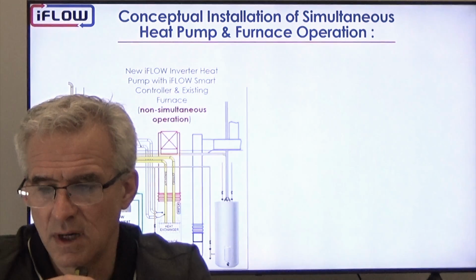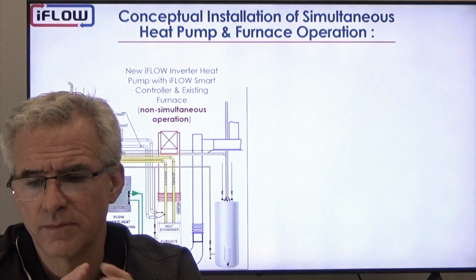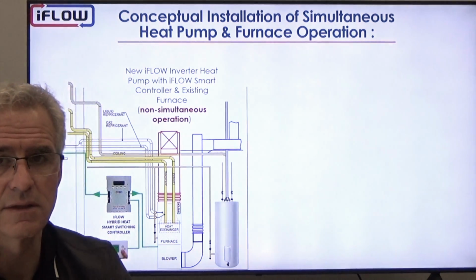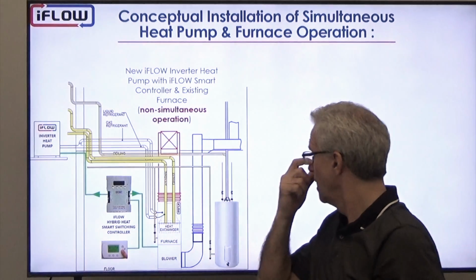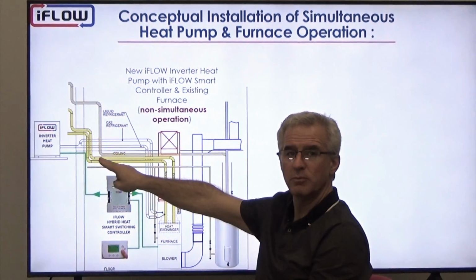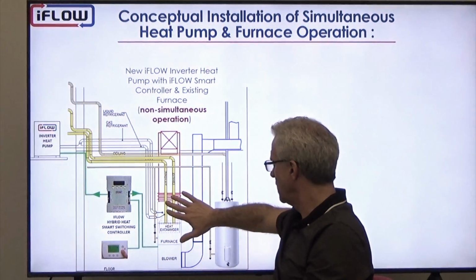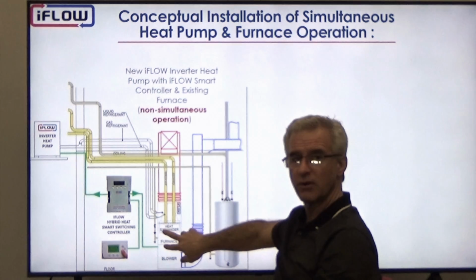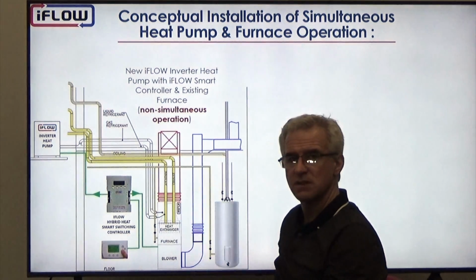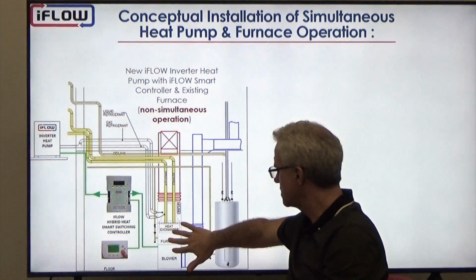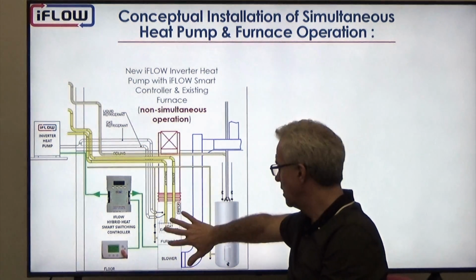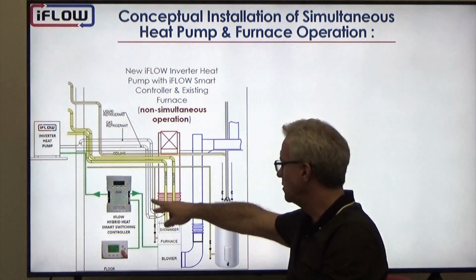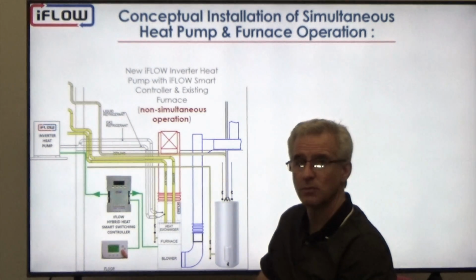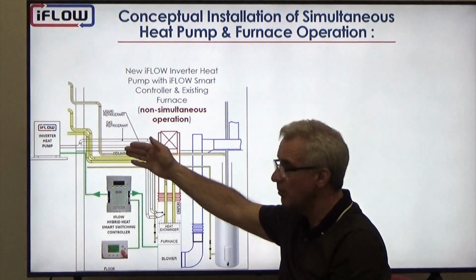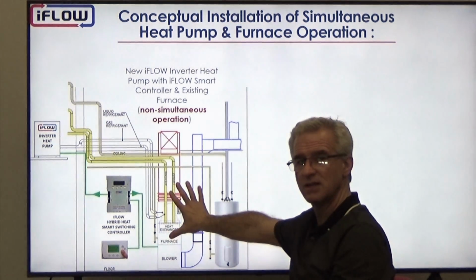In addition, one more feature that is unique to iFLOW: when we're running a combined heating system, like we have on the display here, with the new heat pump instead of the air conditioner, and we're running the evaporator on top of the furnace, we cannot run these systems simultaneously. If you run the furnace at the same time as the heat pump, you're not going to get the evaporation that you need. You'll be sending liquid back to the compressor and it will damage the compressor. So it's either run the heat pump or run the furnace. You cannot run them simultaneously.